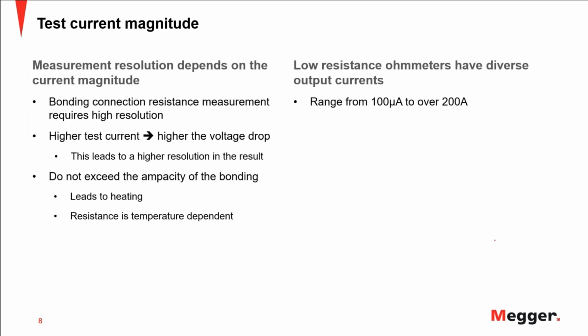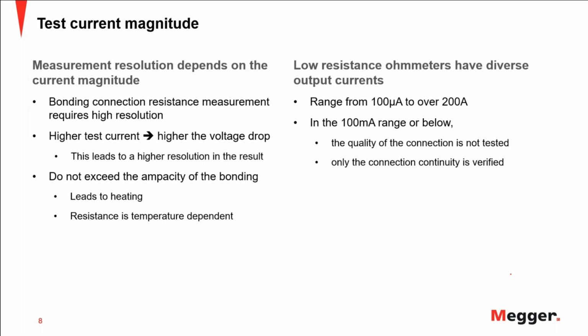Typically the low resistance ohm meters have a wide range. Not in one single instrument, but between instruments you typically see a range from 100 microamps to over 200 amps, and there are instruments that can do 600 amps. Now, for bonding applications and continuity measurements, there's no need of such a high current, and at least you should be above 100 milliamps. Below 100 milliamps, the quality of the connection is not tested. Yes, you get a continuity value, you get a beep indicating that you have a connection, but you are not measuring the real resistance of that connection or the quality of that connection.